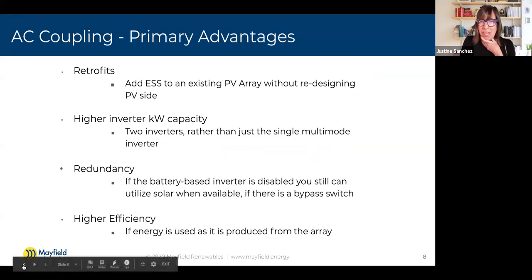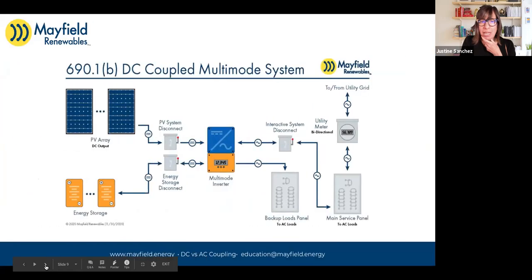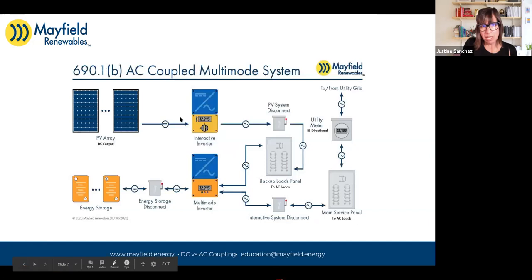So that's another advantage of an AC coupled system. You have 2 inverters, more capacity for feeding those backed up loads, assuming the sources are supplying that capacity. Redundancy, this is one that I hadn't really thought about much before, but if you think about it, in a DC coupled system, you only have 1 inverter. If this inverter is out for repair for whatever reason, even though the solar panels are producing power, you're not going to be able to utilize or backfeed any electricity from the solar into anywhere. If that inverter is gone, your pathway to the AC side of your system is gone. Which means you're not getting credits for those kilowatts you're producing when the sun's shining. So there is some redundancy when you have an AC coupled system.